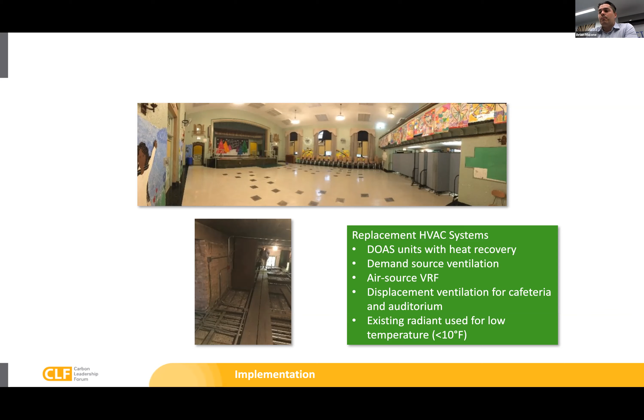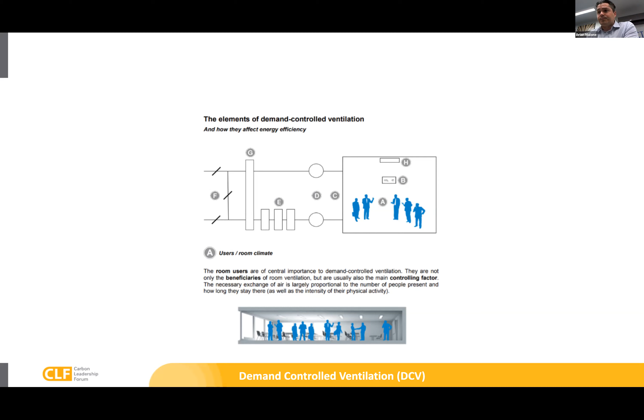Part of the strategies we implemented is demand control ventilation. Certainly, the strategy makes a ton of sense, especially when you have a DOAS system. It's very easy to control. We're able to modulate the supply air into each of the classrooms entirely based on monitoring the CO2 levels in the space. We paired that with energy recovery on the DOAS systems to really reduce the amount of natural gas that we required.